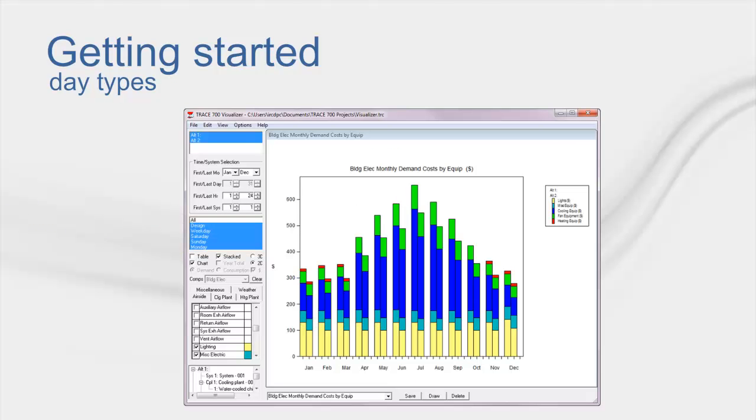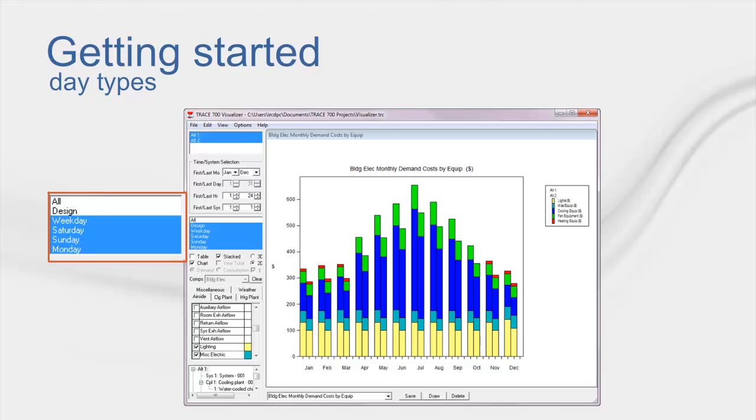This section allows you to see certain day types. It does not show the information of daily values, but it will show only the hourly information for the days that you've selected. You will notice that even if you have a reduced weather profile, you will see a Monday day type that is different from your weekday day type. This is because Trace automatically separates the large pull-up or pull-down loads that normally occur after a weekend drift and puts them on the Monday day type. This helps to make your model a little more accurate because it doesn't account for those loads on every single weekday.